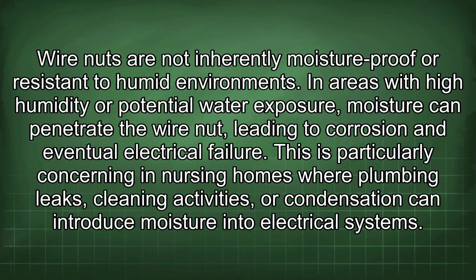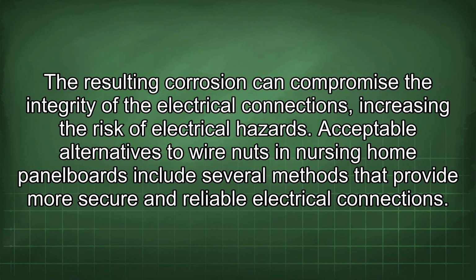Moisture penetration poses a further challenge. Wire nuts are not inherently moisture-proof or resistant to humid environments. In areas with high humidity or potential water exposure, moisture can penetrate the wire nut, leading to corrosion and eventual electrical failure. This is particularly concerning in nursing homes where plumbing leaks, cleaning activities, or condensation can introduce moisture into electrical systems. The resulting corrosion can compromise the integrity of the electrical connections, increasing the risk of electrical hazards.